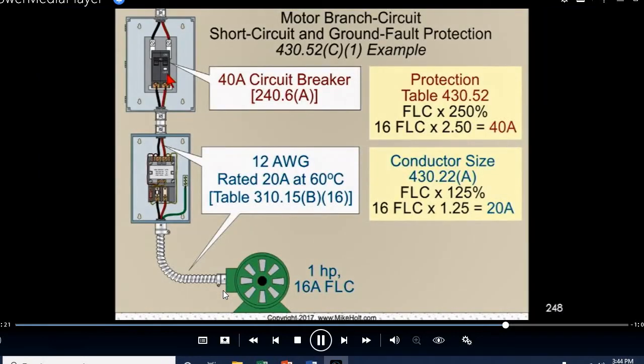So now take a look at the example here. 40 amps? Why have them tied together? Kidding me? That's nothing. Peanuts. You can knock that 40 amp breaker, not a problem, under short circuits and ground faults. But the problem would be what? Overload. That's why we have the overloads. You get the overloads, the short circuit, the ground fault. So now I explained it.